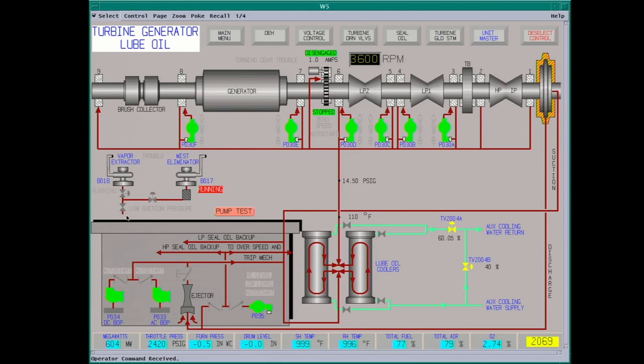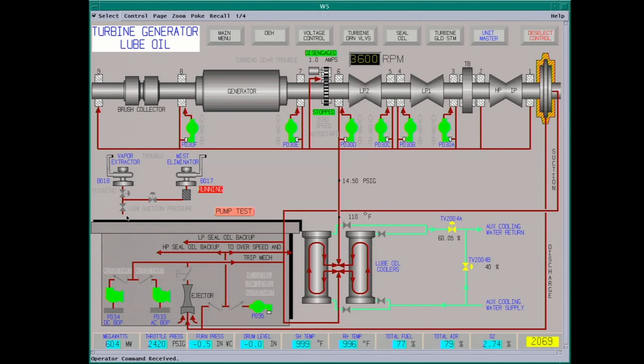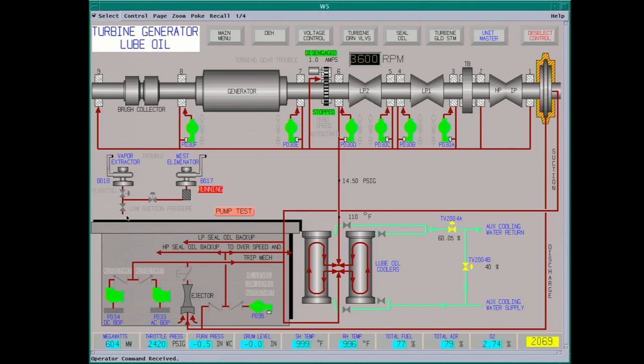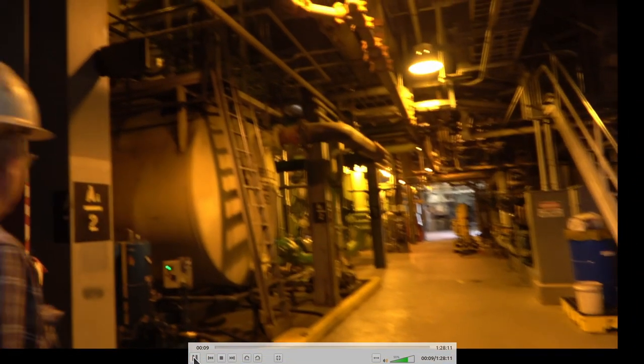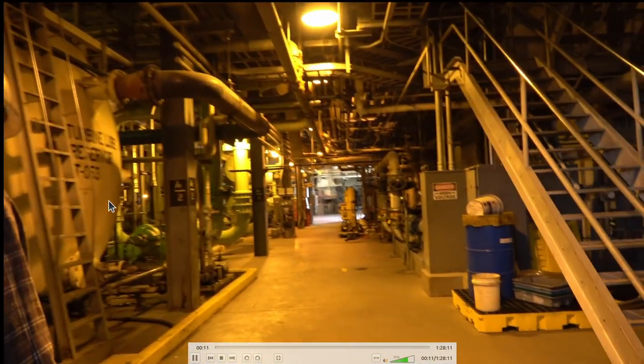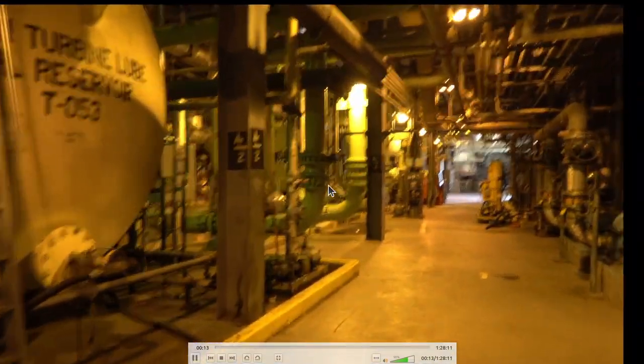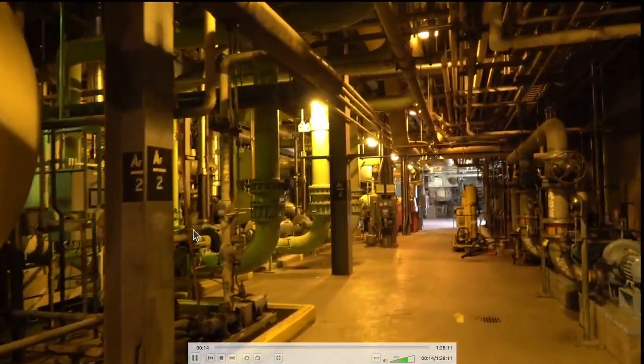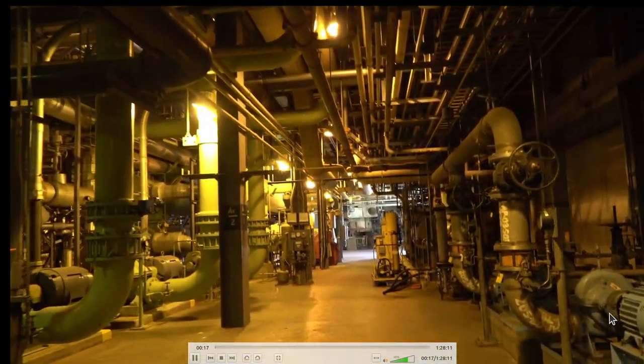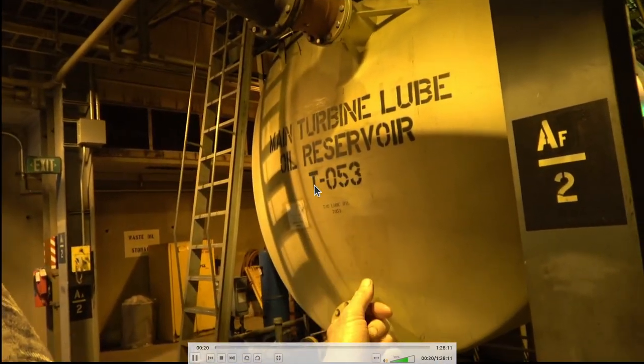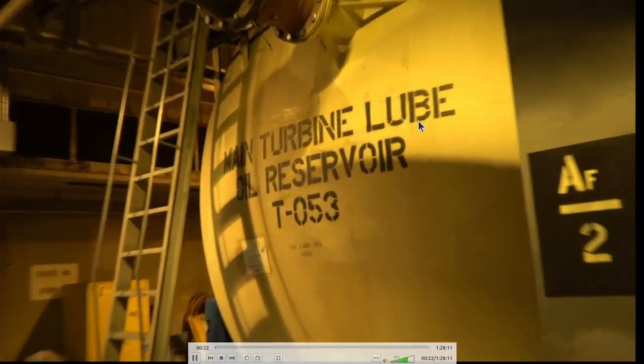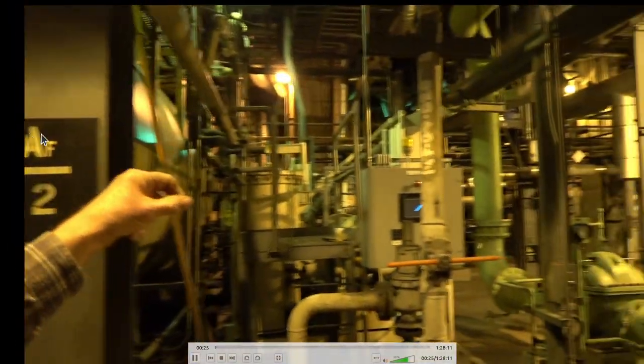These are bearing lift pumps — they keep the shaft off the bearings when it's on turning gear, provide high-pressure oil, and float the shaft. This is the turbine lube oil tank. Over here are the auxiliary cooling water pumps; we'll talk about those later. We have the demin transfer pumps. This reservoir holds about 10,000 gallons of turbine oil 32.